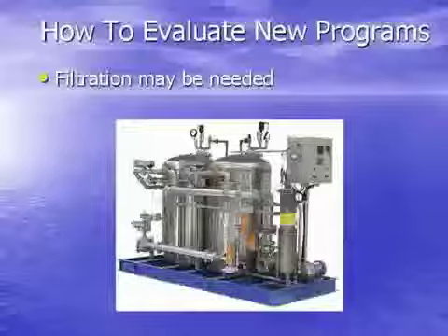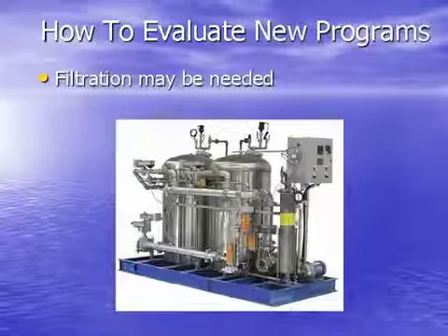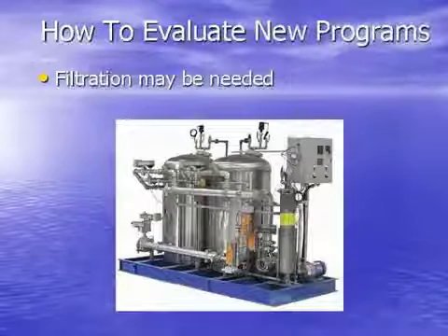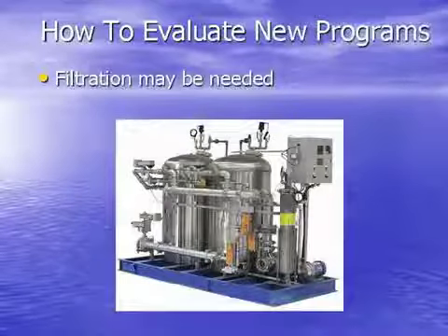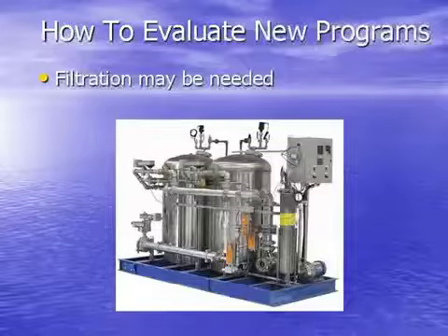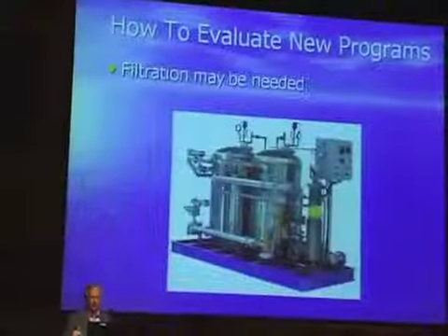And the last thing is, you probably are still going to need some form of filtration. We would recommend this on all cooling towers anyway, because it helps reduce the risk by removing suspended solids. So it's a good idea to have some form of filtration on there, and again, our preference is sand filtration or high efficiency sand filtration.